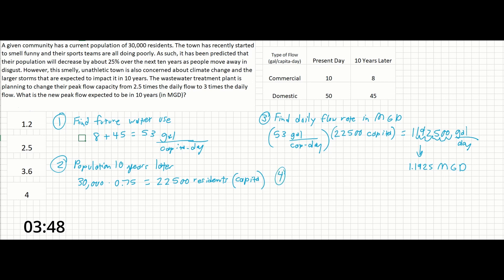And now we have step 4. Find the peak flow in 10 years. The problem tells us that the new peak flow is going to be 3 times the daily flow. So all we have to do here is 1.1925 MGD times 3 and that's going to give us 3.5775 MGD.